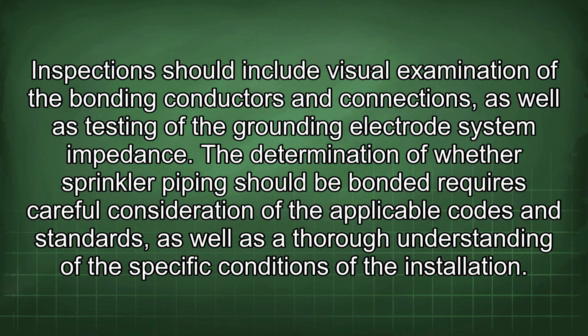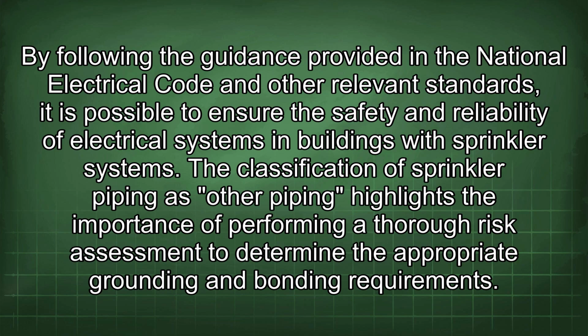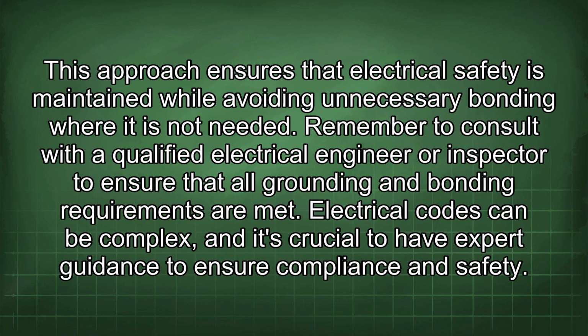The determination of where the sprinkler piping should be bonded requires careful consideration of the applicable codes and standards, as well as a thorough understanding of the specific conditions of the installation. By following the guidance provided in the National Electrical Code and other relevant standards, it is possible to ensure the safety and reliability of electrical systems in buildings with sprinkler systems. The classification of sprinkler piping as other piping highlights the importance of performing a thorough risk assessment to determine the appropriate grounding and bonding requirements. This approach ensures that electrical safety is maintained while avoiding unnecessary bonding where it is not needed.